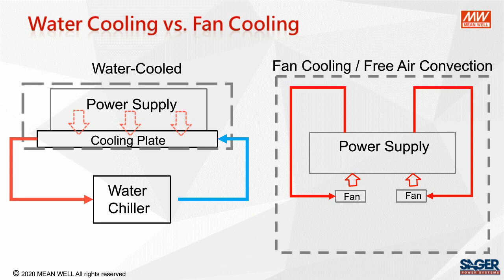On the contrary, for fan cooling, sufficient space is required for the fan to move air effectively. If the power supply is tightly enclosed, the fan will circulate hot air in the system. As a result, the heat from the power supply will affect other components as well. Ventilation holes and mesh enclosure may be used to help with the heat removal from the system, but this also makes the system more vulnerable to dust and water, and makes harsh environment operation more difficult.